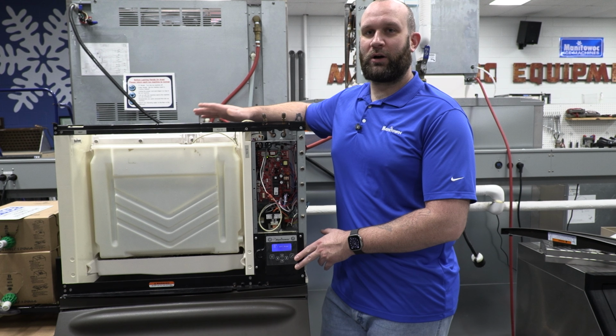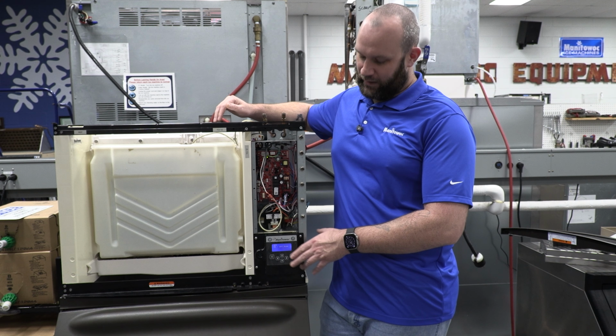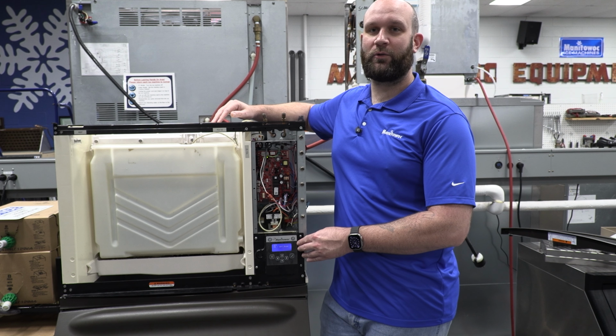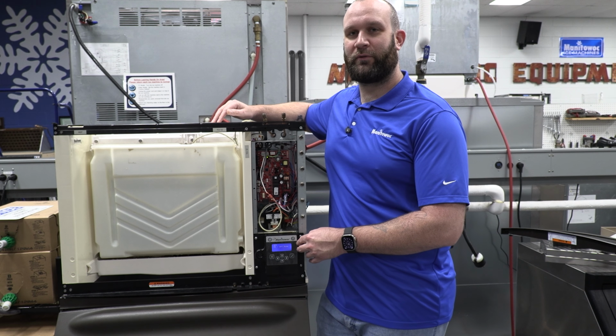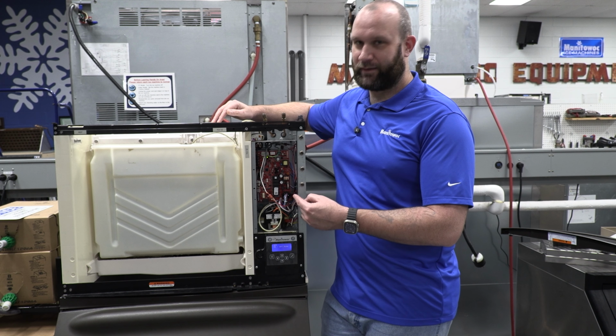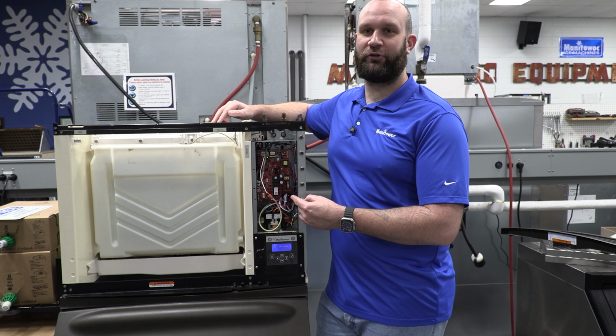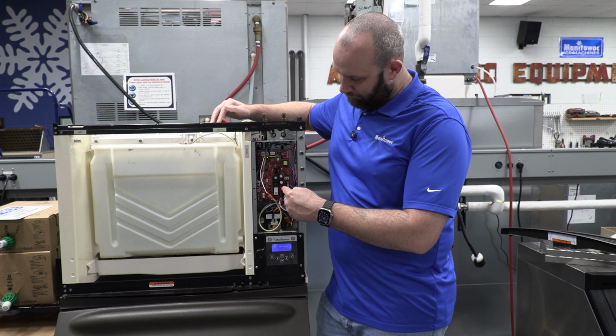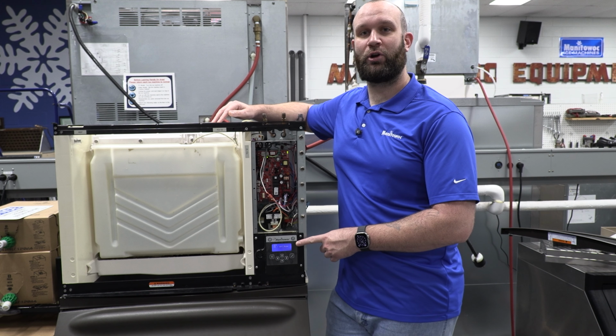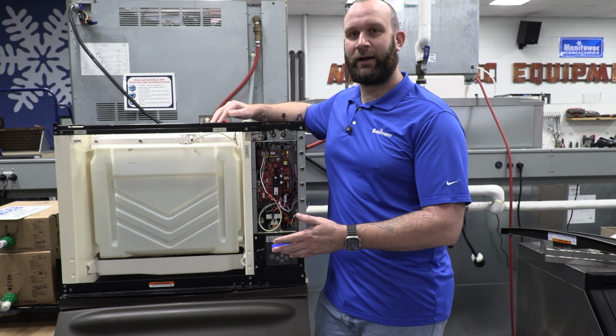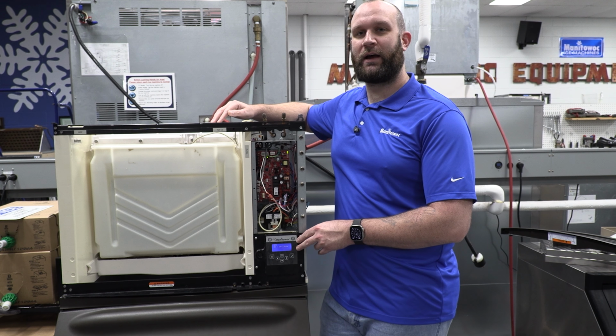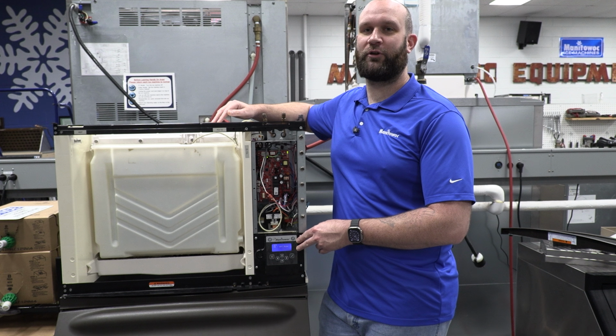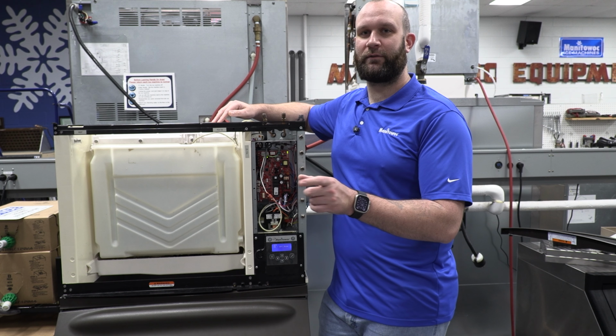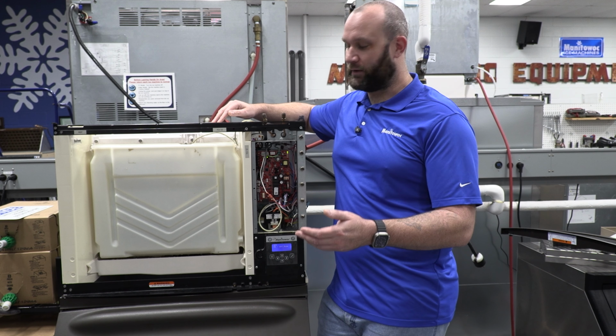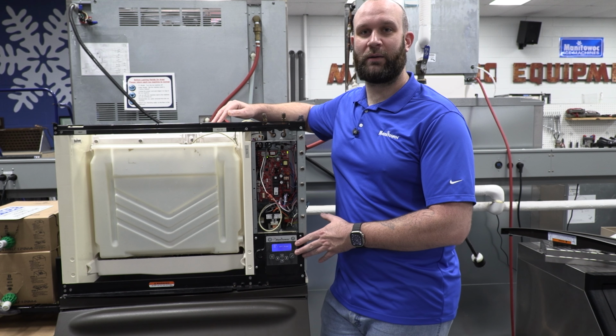So now that I've replaced the water level probe and intermediate harness and we're getting the proper input reading to our control board, the last thing I would do before wrapping up this service call is update the control board to the current revision of firmware. As long as you have a red control board in your Legacy Indigo machine, it is able to be updated. You can find the latest revision at manitowocice.com/service. Scroll down until you see firmware update, download the file to your flash drive, and complete the upgrade.